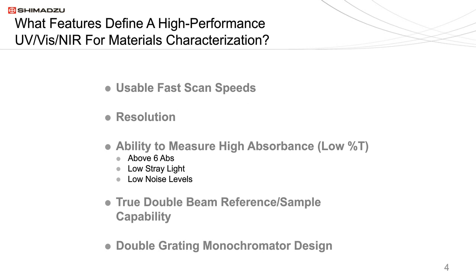What features define a high performance instrument for the materials characterization market? First, usable fast scan speeds — most of these applications are quality control where sample throughput is an issue. Second, resolution — many of these samples are solid and have narrow band peaks that need to be resolved. Third, the ability to measure high absorbance or low percent T, usually above six absorbance units, which relies on very low stray light and low noise levels. Fourth, true double beam capability so that you can reference beam attenuate. And fifth, double grating, which is not always required, as we'll see.